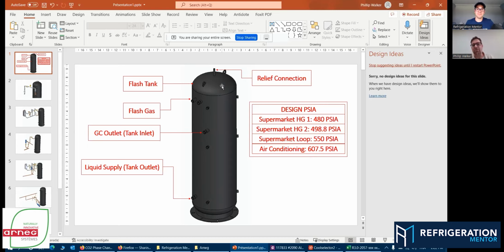These tanks for supermarkets are producing 5,000 to 7,000 pounds of flash gas in transcritical. So we have to leave a little bit of room for that flash gas, because contrary to myth, it's not just being dumped 100% into the suction header.